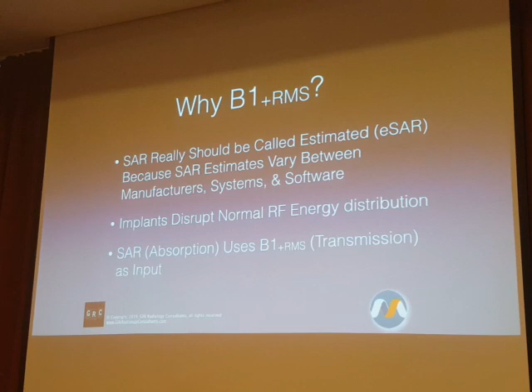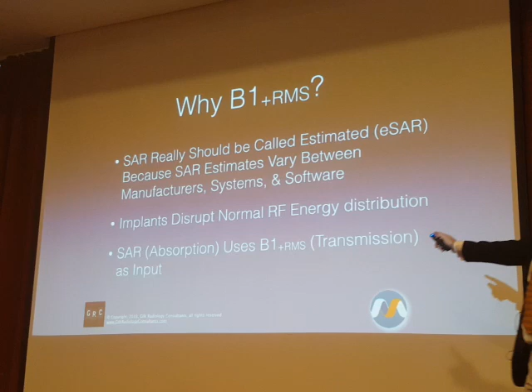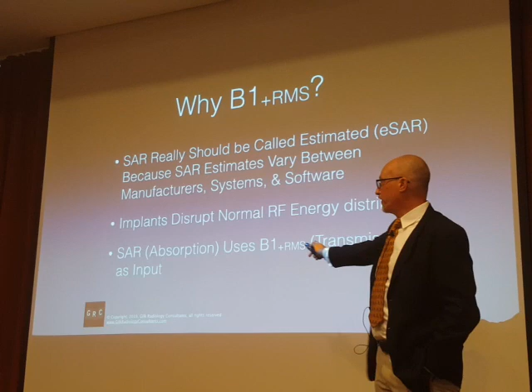So as I mentioned, SAR should really be called ESAR, estimated SAR, because it varies tremendously. Implants totally mess up SAR distribution and SAR predictions. So for implant devices, if you can use B1 RMS, if your system supports it, you may find that more advantageous. And then one last bit about diffuse versus focal heating.